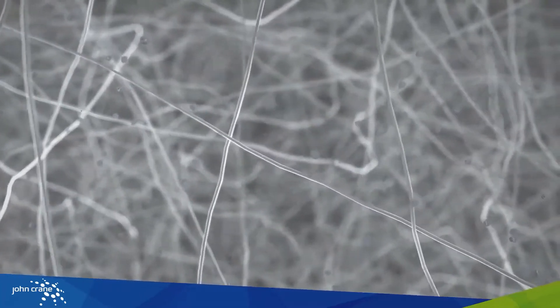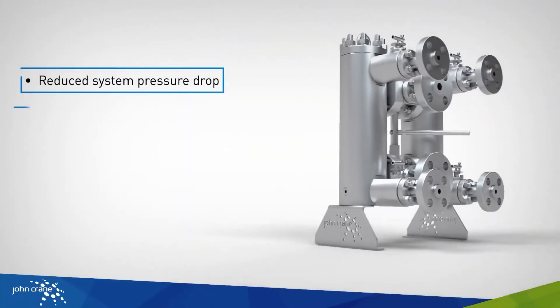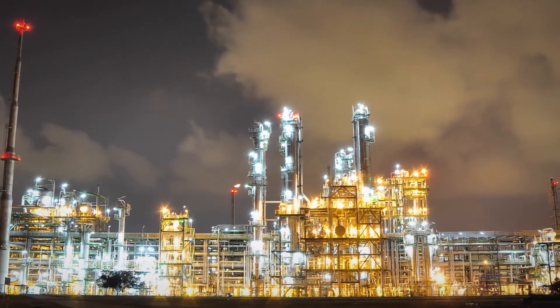New hydrophobic treated filter media improves droplet drain speed. As standard, contaminants of one micron and smaller are removed at efficiencies of 99.9%. The new John Crane seal gas filtration system delivers significantly reduced pressure drop and optimized process flow, with up to 50% lower pressure drop both at startup and in operation, plus increased flow capacity of up to 60%.